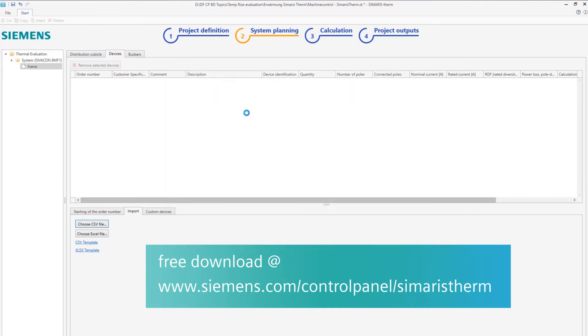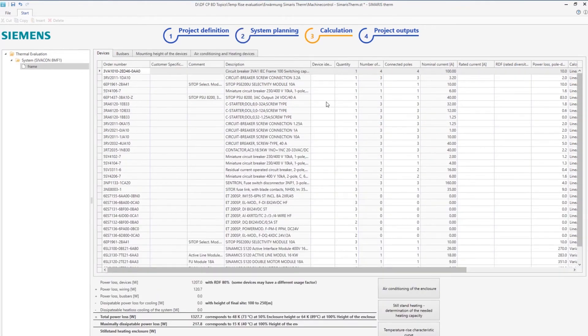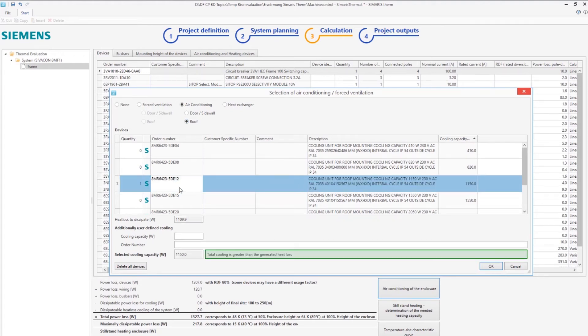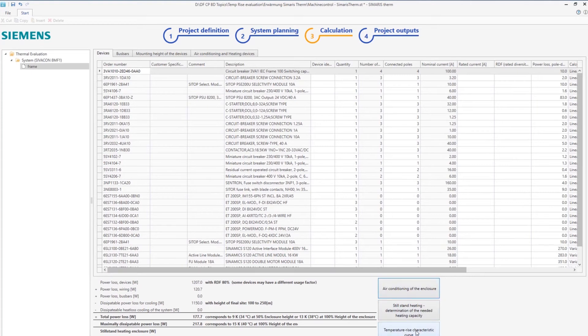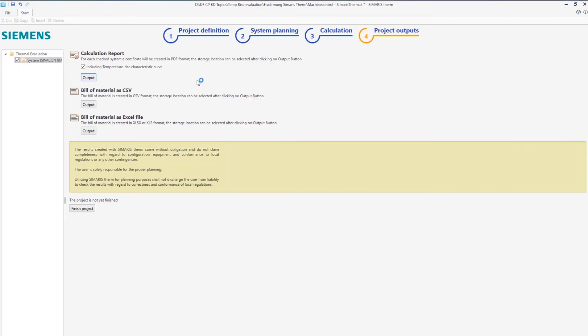The calculation method of SIMARIS Therm supports the general thermal calculation method as well as the advanced temperature calculation in accordance with the relevant EN IEC 61439 standard for low voltage switchgear applications. SIMARIS Therm supports you effectively in planning and engineering your switchgear and control gear assembly. The tool also conveniently supports you in selecting predefined or individual cabinet structures, housing, or electrical devices. The user interface with its flexible device import functionality enables you to efficiently import your bill of materials in CSV or Excel format.